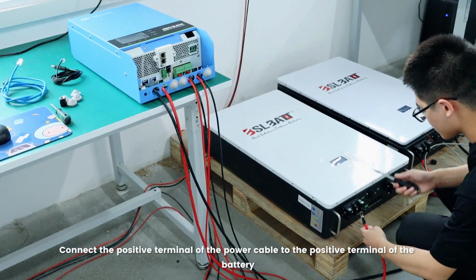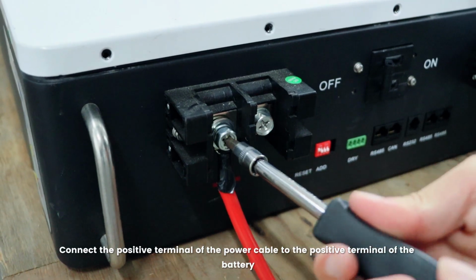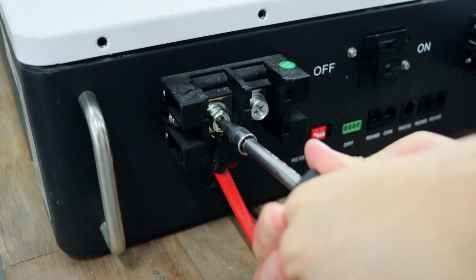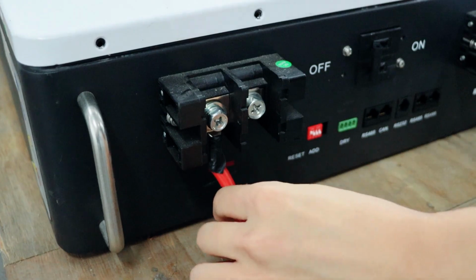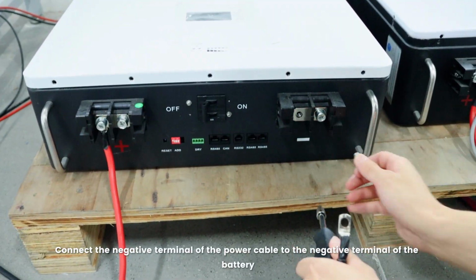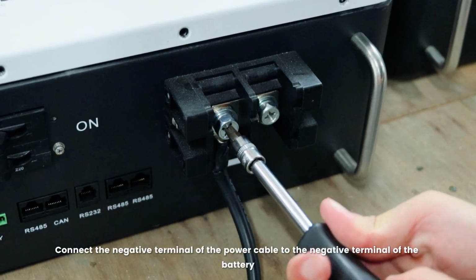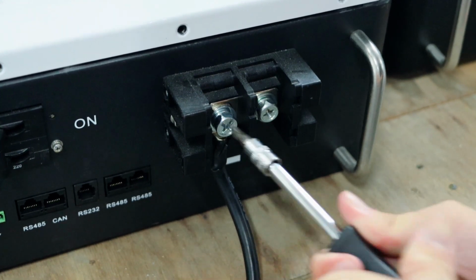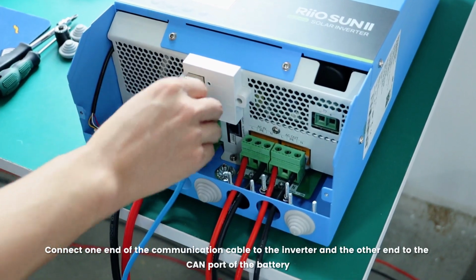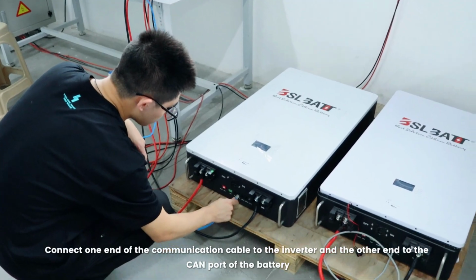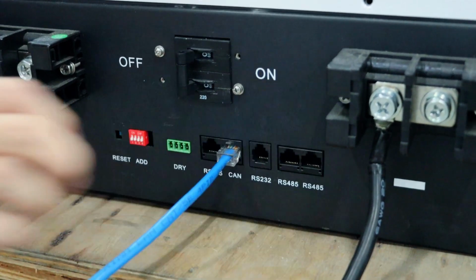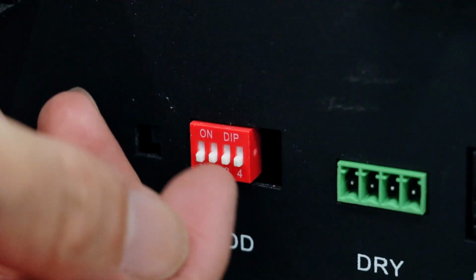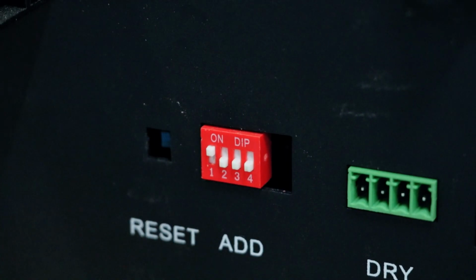Connect the positive terminal of the power cable to the positive terminal of the battery. Connect the negative terminal of the power cable to the negative terminal of the battery. Connect one end of the communication cable to the inverter and the other end to the CAN port of the battery. Set the dip switch to 1.